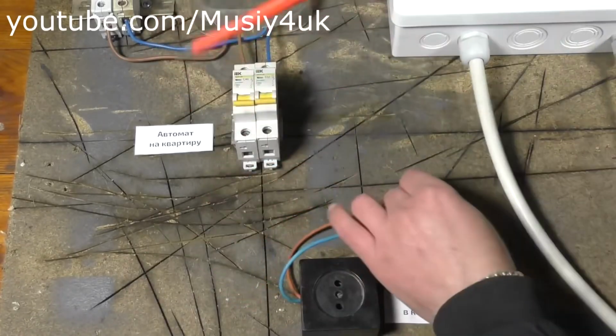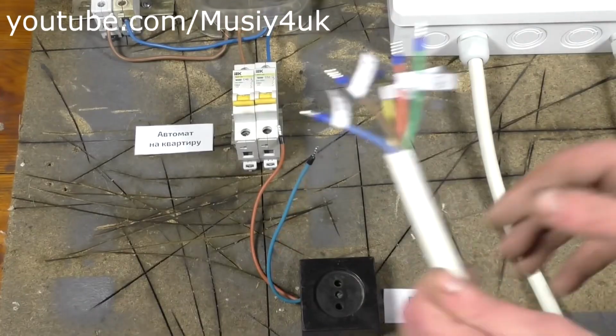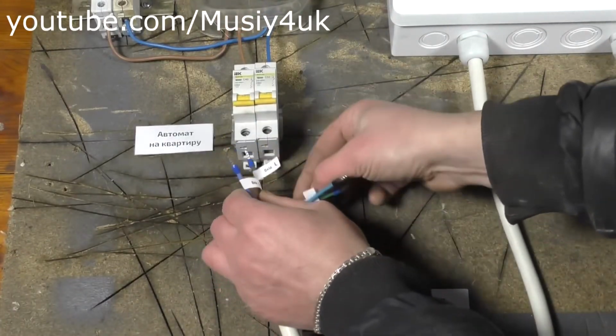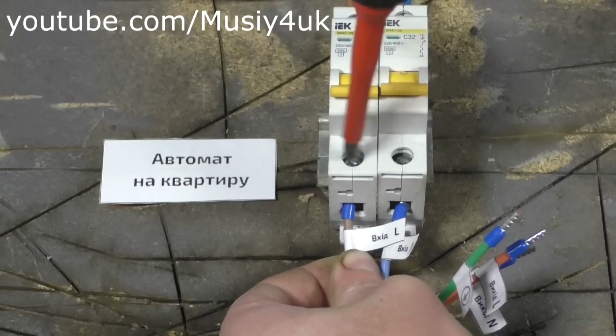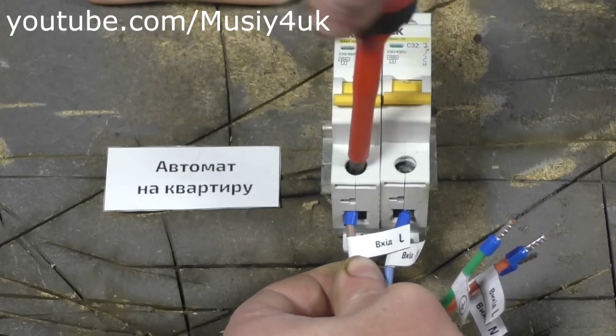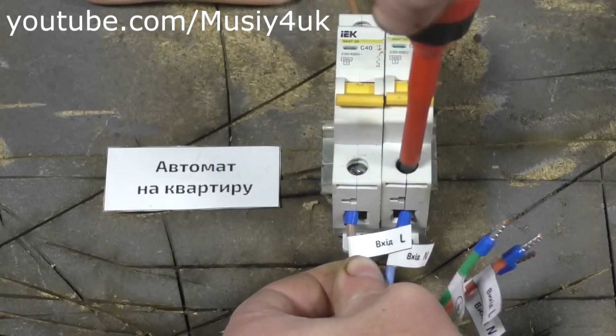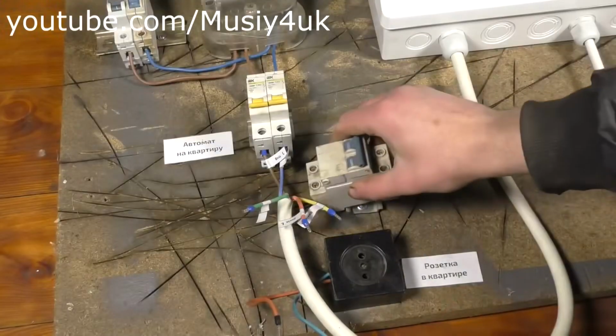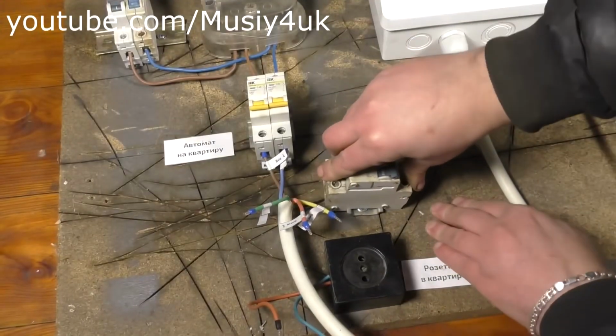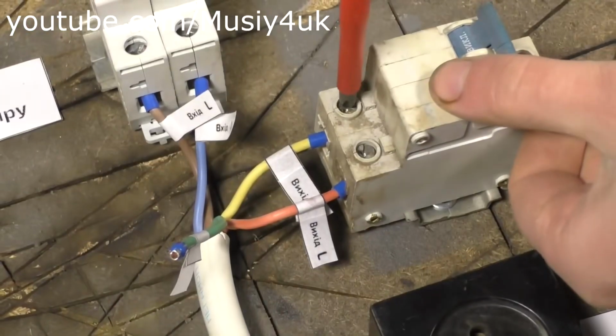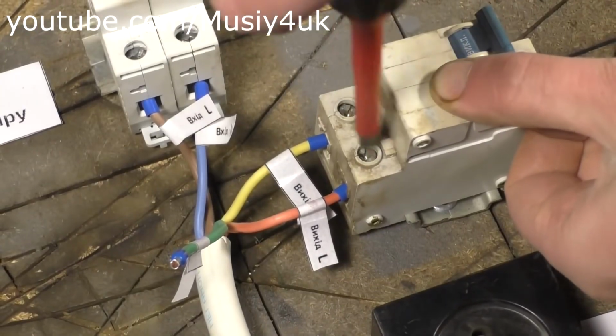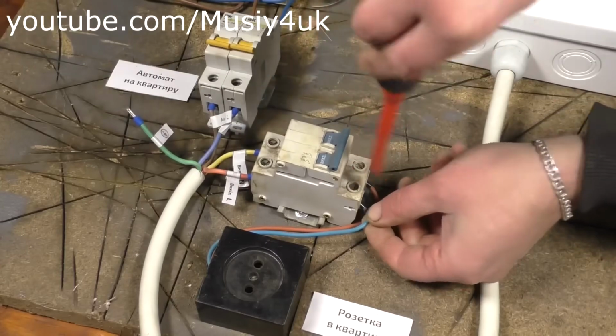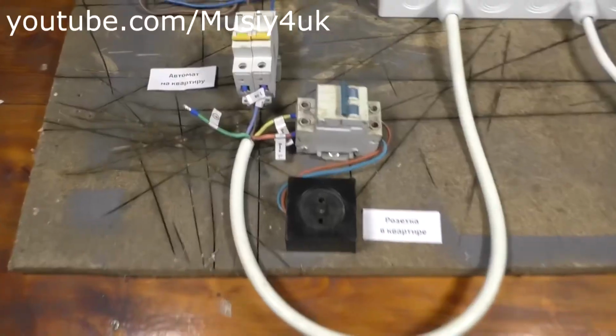Next, you need to connect the wires from the automatic transfer switch panel to this breaker, which are labeled as input. The phase will be on the left and neutral on the right. Next to this breaker, you need to install one more additional breaker. After installing the breaker, connect the output wires from the automatic transfer switch panel. The phase and neutral sides don't matter here. And to the output of this breaker, you connect the wiring that goes to the apartment.